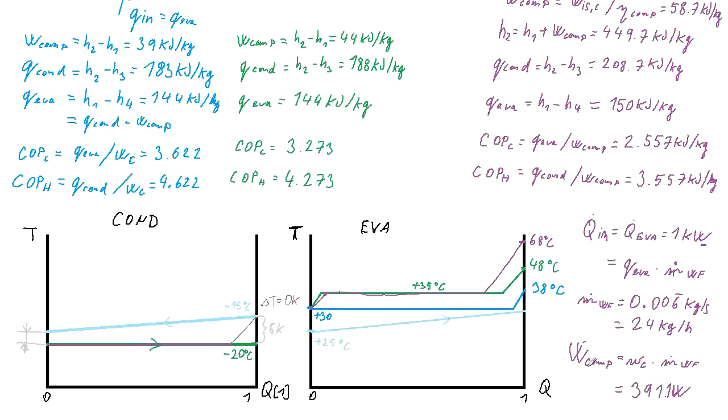So the thermodynamic input into the compressor is about 390 watts. If we include some electrical efficiency, eventually some frequency converter, the electrical input into the system would be about 400 watts.